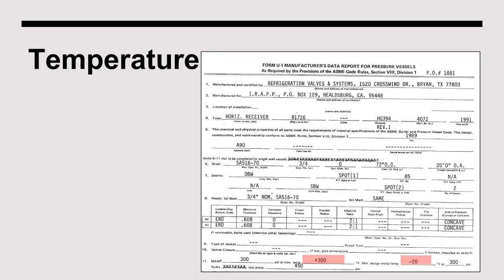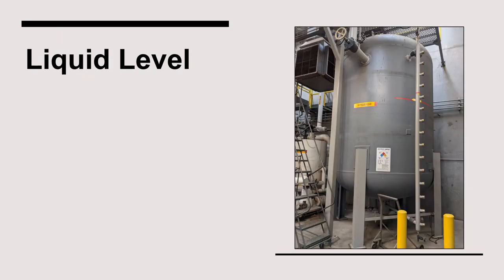As with MAWP, the maximum and minimum temperatures are also displayed on the U1 form. Liquid ammonia needs room to expand if the vessel experiences an unexpected heat load. IIAR Book 1 recommends that it is good practice to limit the liquid level to no more than 80% liquid, leaving 20% of the vessel volume as room for expansion. The 80-20 rule is based on the actual expansion change seen in anhydrous ammonia liquid stored at minus 65°F and allowed to warm up to 125°F.